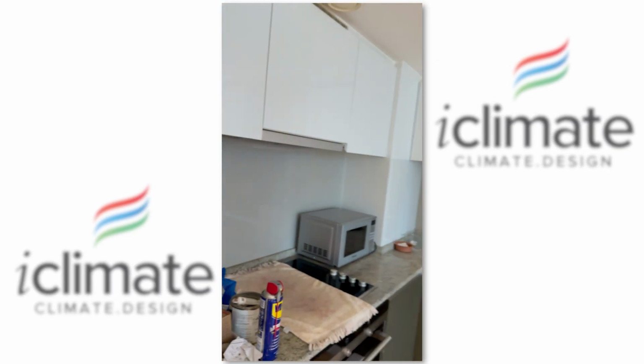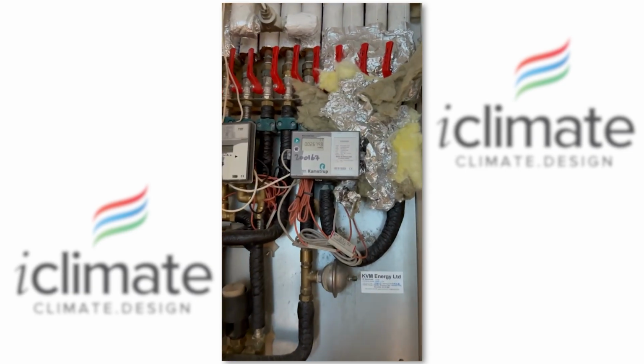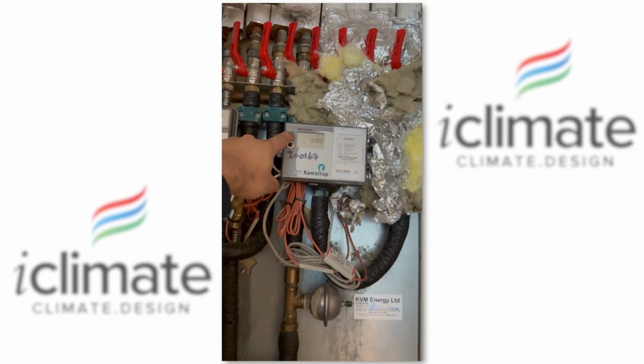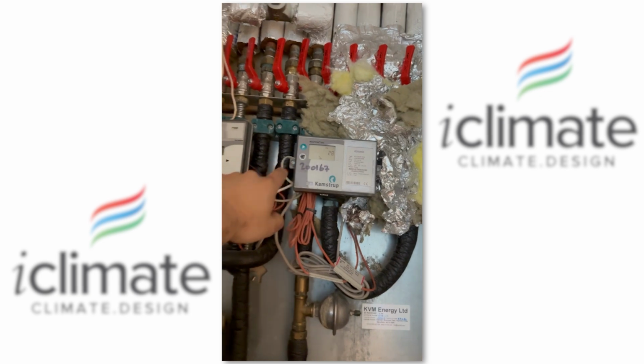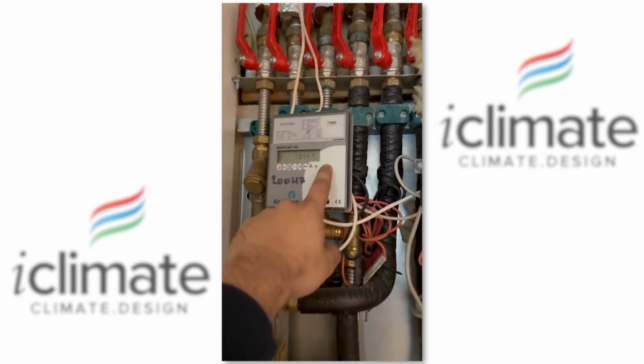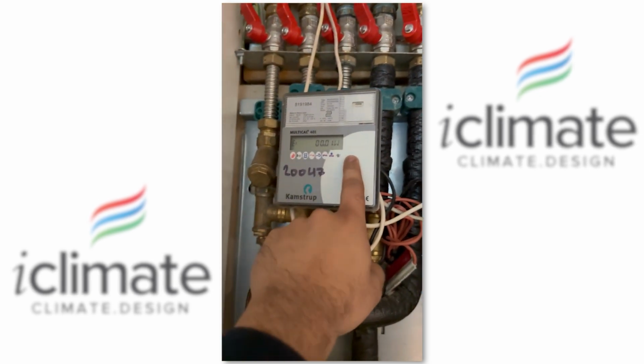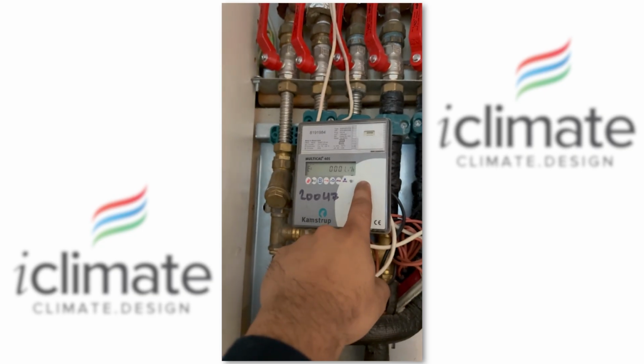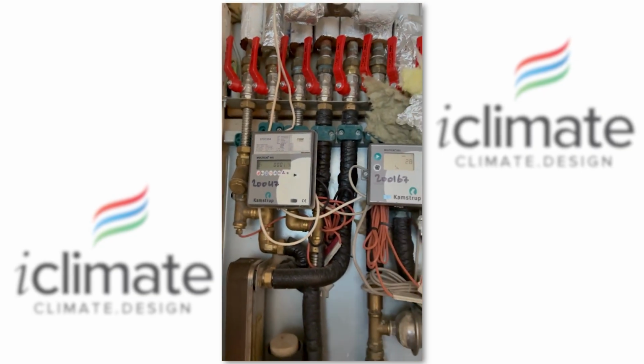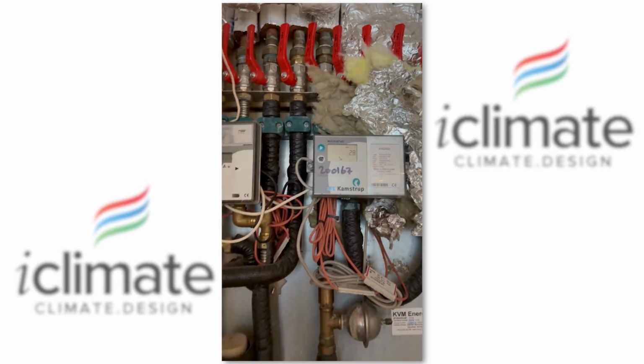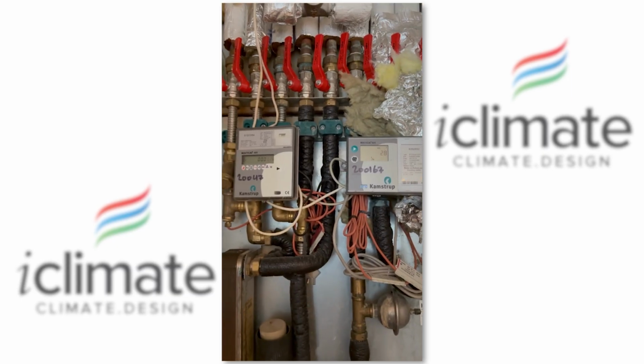We just need to prove that we are getting flow through the flow meter on the cooling side, and we are at 28 litres now on the cooling side. If you look on the heating side, we have nothing because heating is off. We're going to quickly change this over to proof flow and leave this job finished.